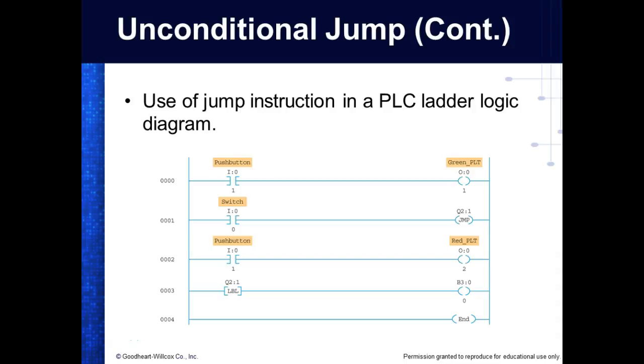Like if I'm red, I want you to jump to this part of the program. Well, that's conditional, because this is unconditional. Yeah, unconditional means it would always go. So in my opinion, unconditional wouldn't have anything. That would be a situation where we want to take out a section of a program and still want the rest of it to run, so we could just put a jump and jump over the section that we don't want to do.